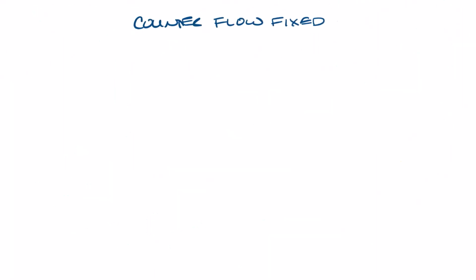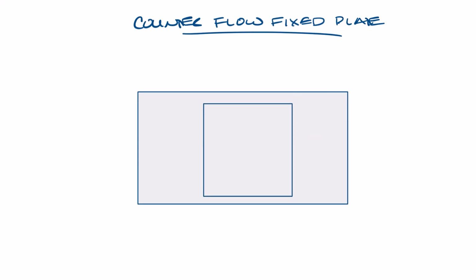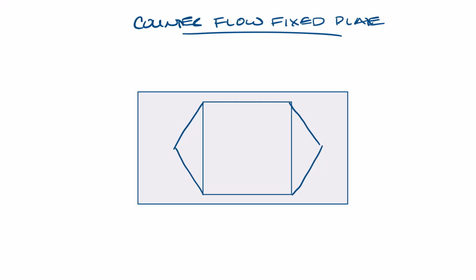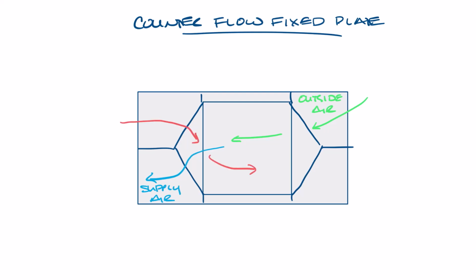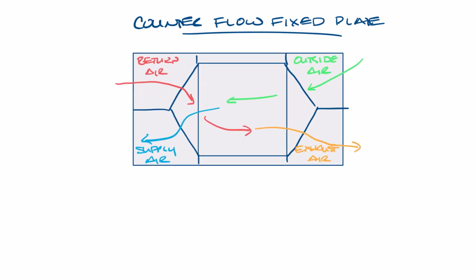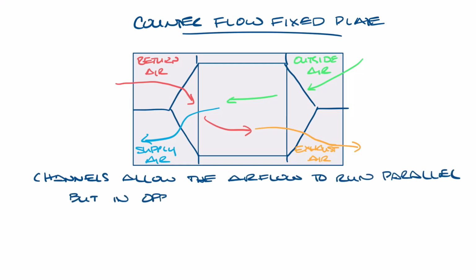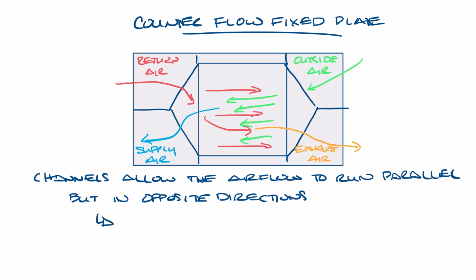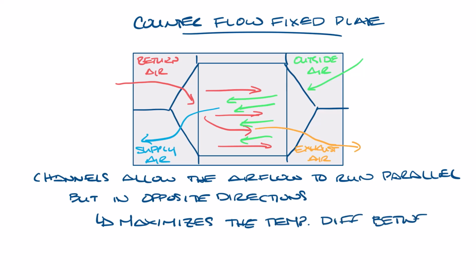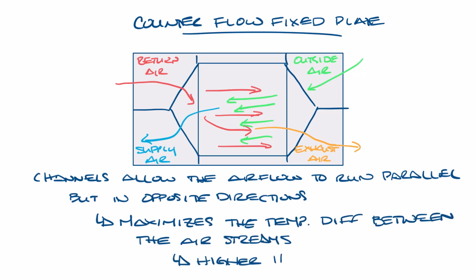Counterflow plate ERVs kind of look like this. Again, we have a cabinet, and we've got the fixed plate core here in the center. And then the air streams are separated again. Outside air comes in here, passes through the heat exchanger, and then goes out to the supply air down here. Return air comes in here, passes through the plates again, and exits as exhaust through here. Let me move this up just a little bit. So again, there are channels in here that are directing the airflow in one direction or the other. These channels allow the airflow to run parallel to each other but in opposite directions. Because the air streams move in opposite directions, it maximizes the temperature difference between the air streams, leading to higher heat exchange.